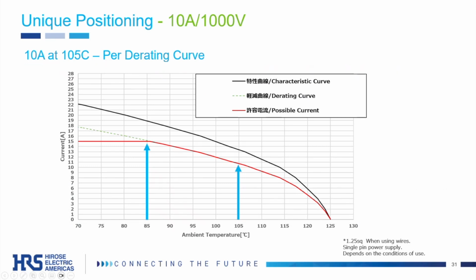This slide shows the unique performance positioning, the 10 amps and 1000 volt combination with no apples-to-apples competitors found yet. The derating curve shows 10 amps at 105 degrees Celsius ambient and around 15 amps at 85 C. This capability fits two key applications: emergency discharge circuits in high voltage inverters and battery thermal control, for example, pumps and heaters. Both need real current, not just signal, and both are growing quickly as the industry moves from 400 volt to 800 plus voltage power lines.